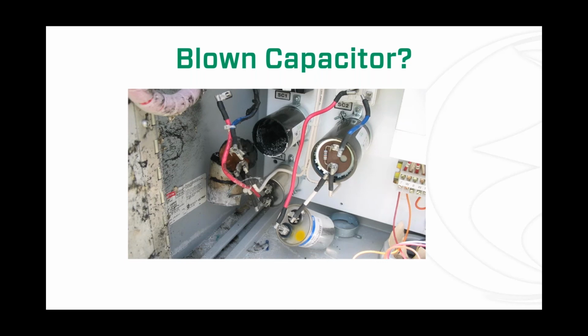Sometimes when they fail, it's not a spectacular explosion, it might just be a little leak and oil seeps out of them. If the oil leaks out, that means your capacitor is bad and you're going to have to replace it.